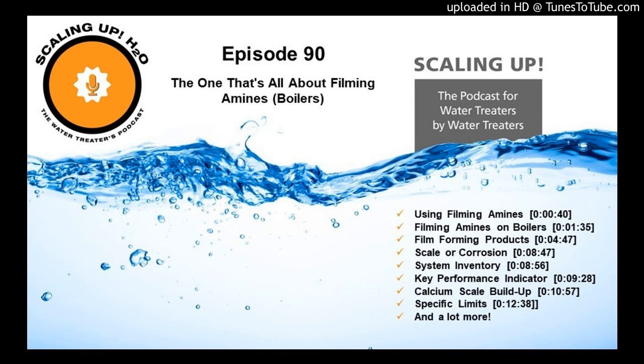Then all of a sudden, there's even more little niche space for the filming amines to go. And I don't want them to go onto debris that we're going to blow down that we don't want in there. I want them to go onto your pipes. I want them to go on the surfaces that we have a goal for coating. So I don't want to use up the material or the filmers, if you will, on a spot that ultimately I want to go down the drain.